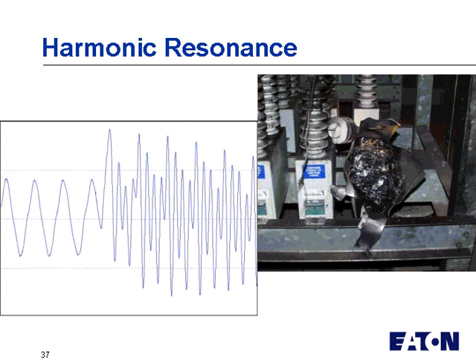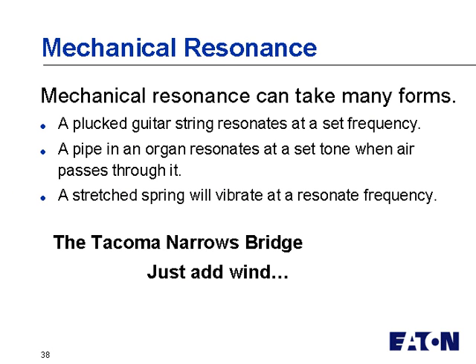Now, we mentioned harmonics a few times, and what's the big deal with harmonics? Well, we have to consider harmonic resonance if we're going to apply power factor correction solutions, especially if we're just going to put power factor correction capacitors on the system. If you look here, the waveform on the left shows a nice sinusoidal waveform, and then all of a sudden it goes crazy. Well, what is that craziness? That is harmonic resonance. And if you look on the right, that's a failed capacitor from a medium voltage larger installation where it actually caused resonance, or the resonance caused failure.